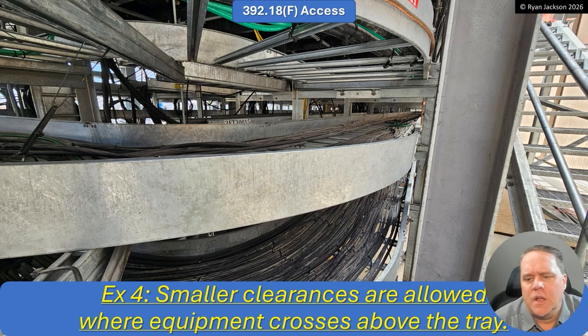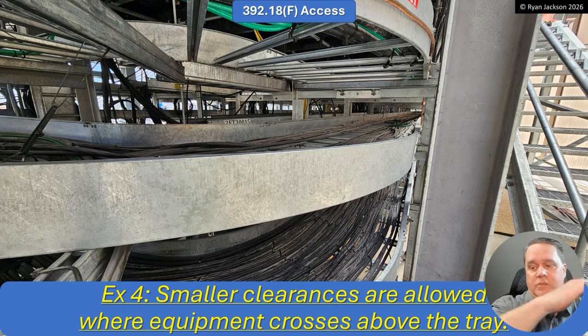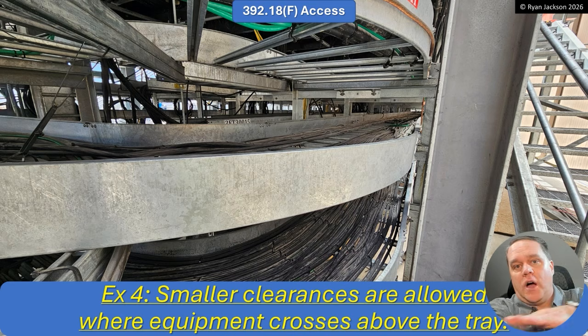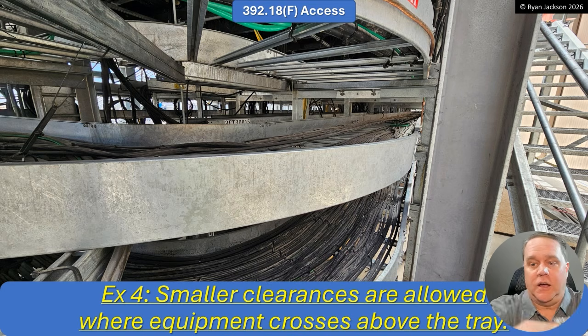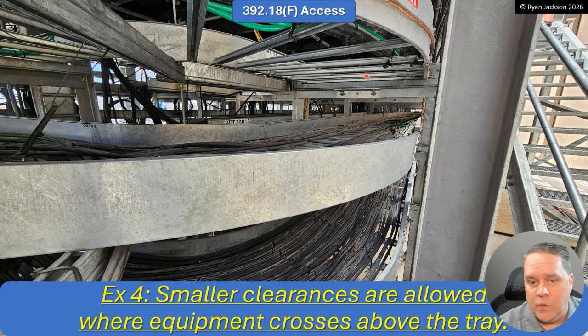And then the other exception, smaller clearances are allowed where equipment crosses above the tray. So when it says crosses above the tray, I guess that means perpendicular, right? So the cable tray is here and something else crosses this way. Whereas if it's parallel, like here in the picture, we've got one going the exact same way, right? They're all concentric bends following each other. Is that okay if that was less than 12 inches? Is that an example of equipment crossing above the tray? Maybe. You could argue that.